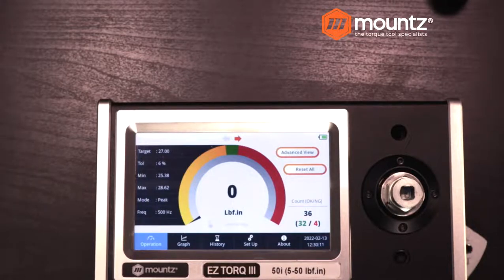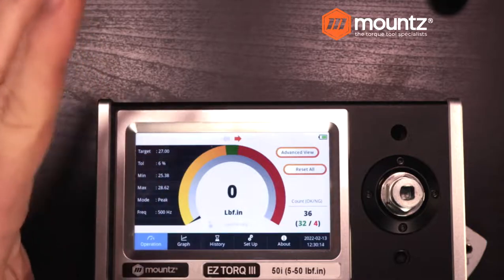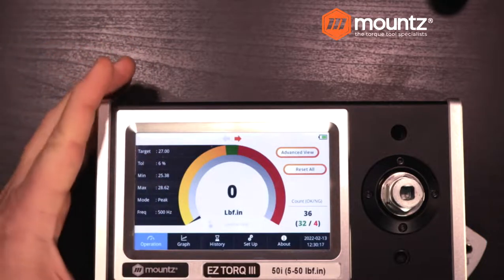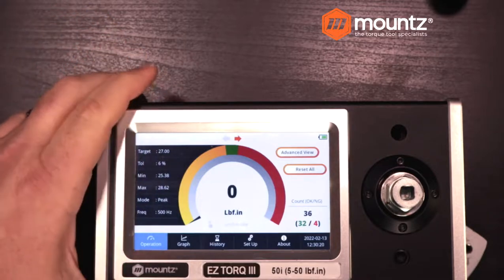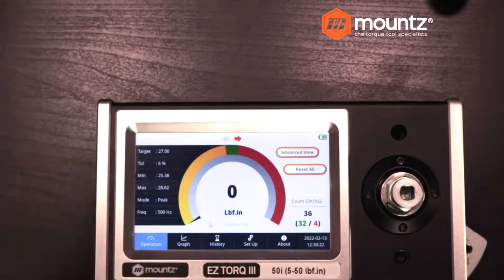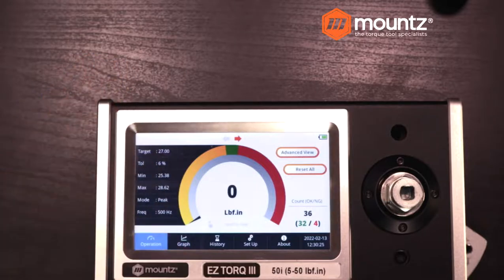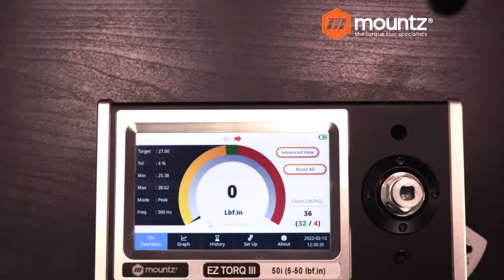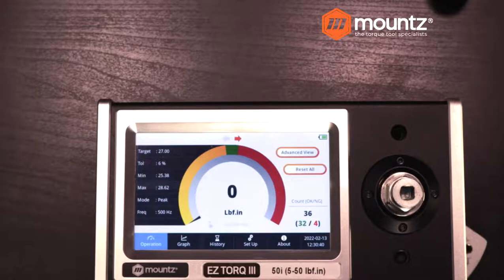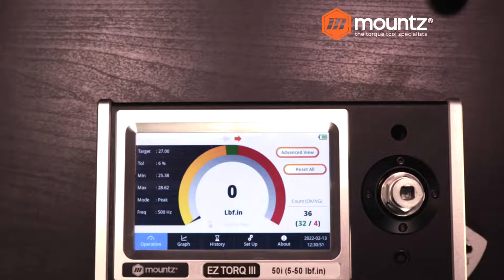This process gives you the ability to trace the readings from the analyzer certificate to the dead weights that were used to calibrate the analyzer, and then all the way back to the standard for those particular weights. If you have any questions on how torque analyzers are calibrated, that is another presentation we have available. That is the conclusion of today's presentation — let's go ahead and move to any questions that we may have.